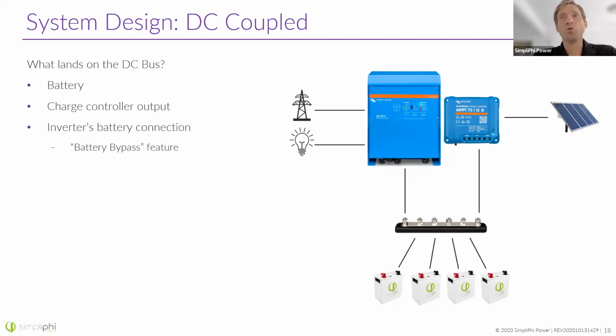I guess in terms of what you do with that power coming out of your array, there are some settings in your inverter, right? If you're in a location where you are able to feed back to the grid, you could set your system up so that the power that's coming into the batteries, let's suppose the batteries fill up, you can still use that inverter to draw power out of the panel and send it back to grid or send it to loads. But that's an excellent point that I want to point out. And I've used this example and tried to push this example with Daniel in our trainings, and that's that you can kind of think of solar panels as rain capture devices or water pumps. And essentially, if there's nowhere for the energy that's striking a solar panel to go, then that panel is actually not producing any energy, right?